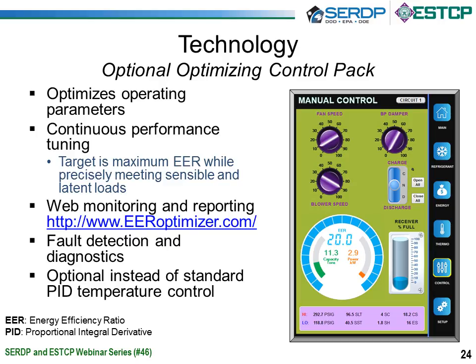This is done really one of two ways. The most elegant one is the optimizing control package that goes with the technology. This one optimizes the operating parameters and takes best advantage of what the ClimateStat refrigeration side is able to offer. It continuously tunes all of the operating parameters of the air conditioning with the target being the maximum energy efficiency ratio. It has features like web monitoring, fault detection and diagnostics. This would be optional instead of the standard PID temperature control that's used with ClimateStat.